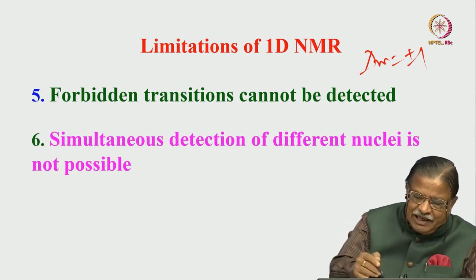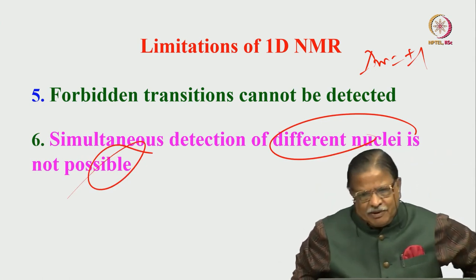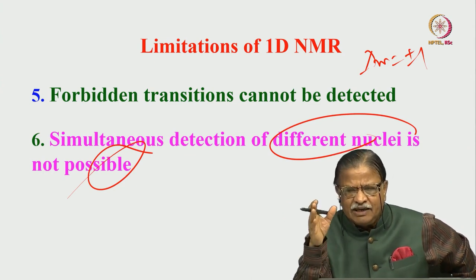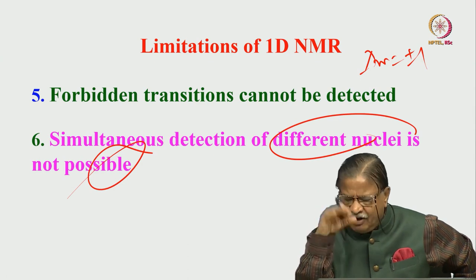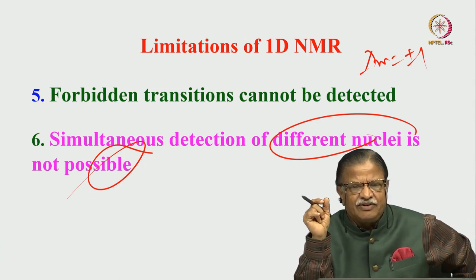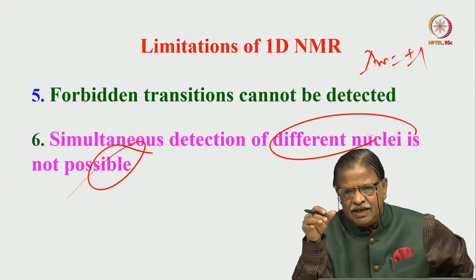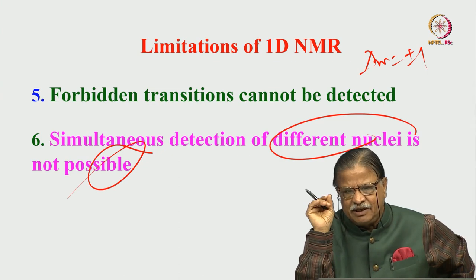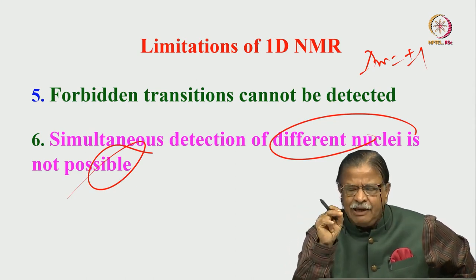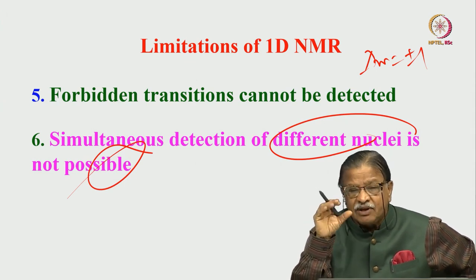Another limitation is that simultaneous detection of different nuclei is not possible. If I want to take a 1D NMR spectrum of proton at 400 MHz, I tune the probe and get only the proton signal. If I have to do carbon-13 NMR on the same spectrometer, I have to change the frequency of the probe. Both proton and carbon-13 cannot be detected simultaneously. These are all limitations of 1D NMR — they put certain constraints on what you can do.